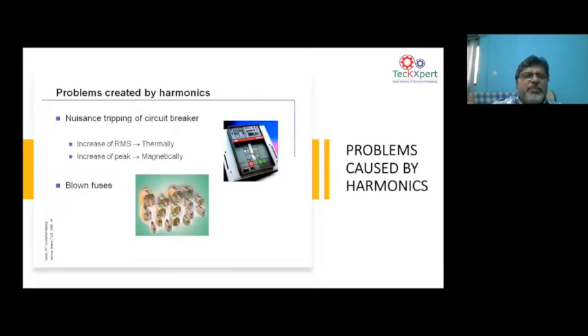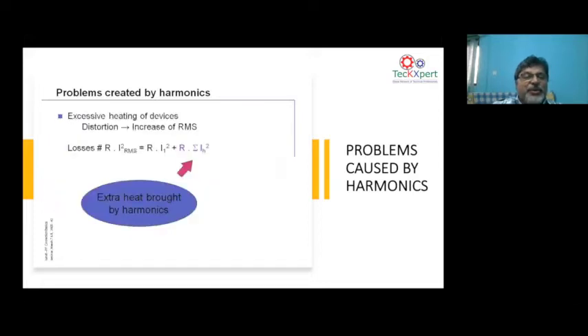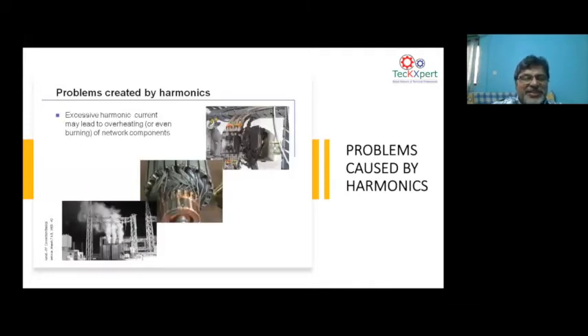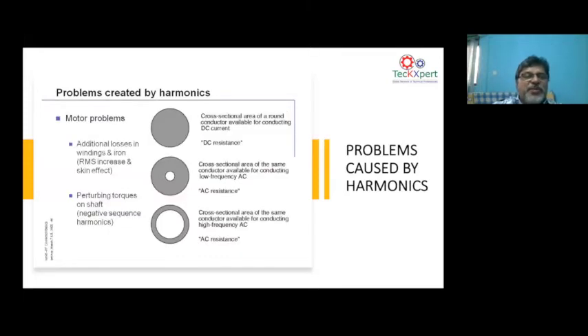Okay, typical problems created: as I said, the tripping of the breaker, blowing of fuses, and then the higher I2R losses. When you say higher losses, you can see the next picture. Something is burning out, this is your motor or your breaker or your transformer burning out. These are all the problems of harmonics.